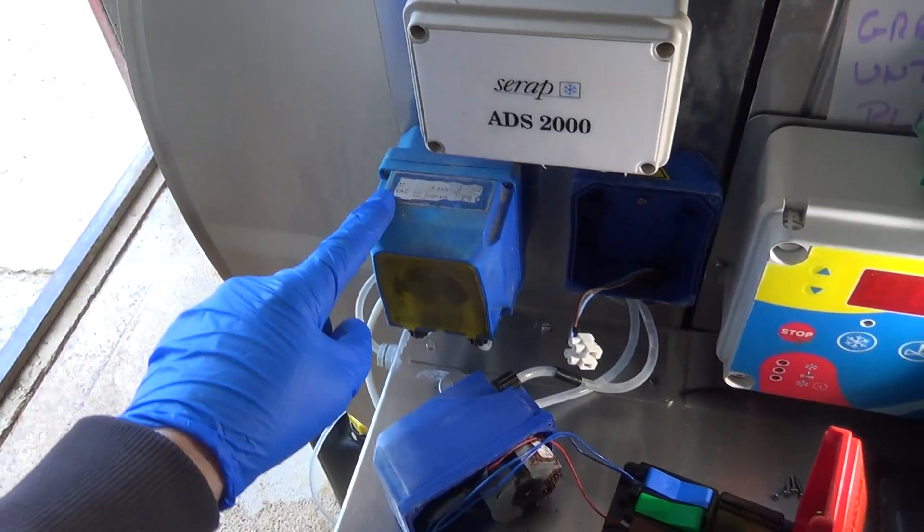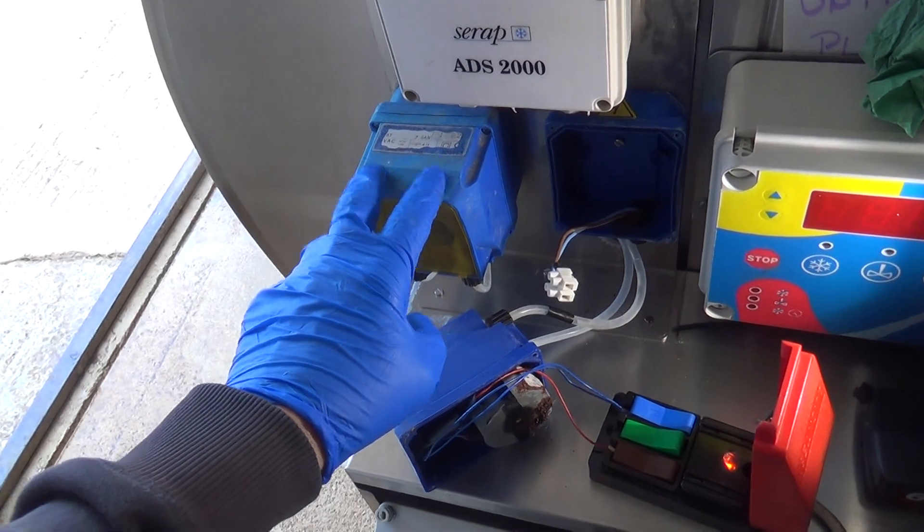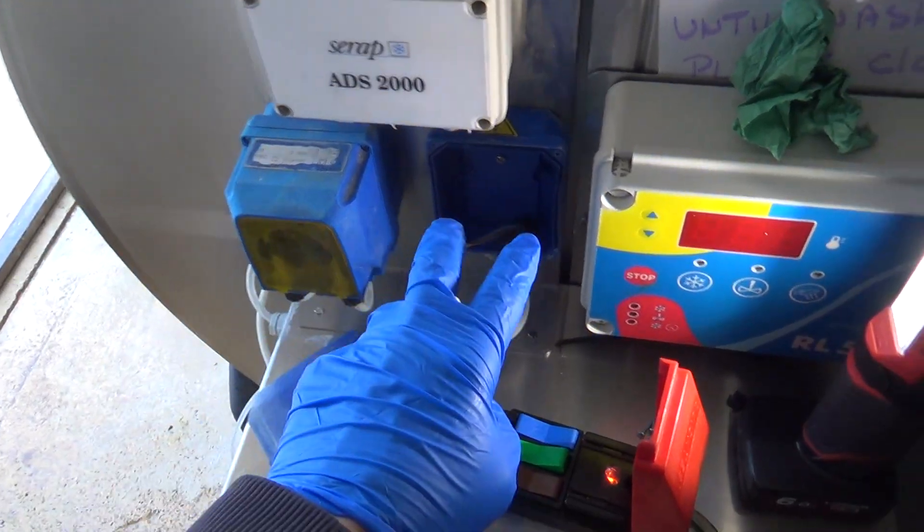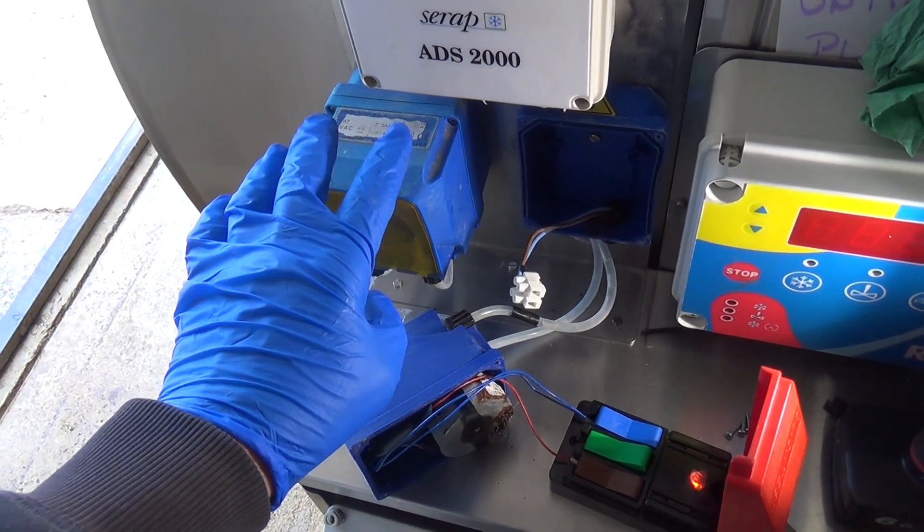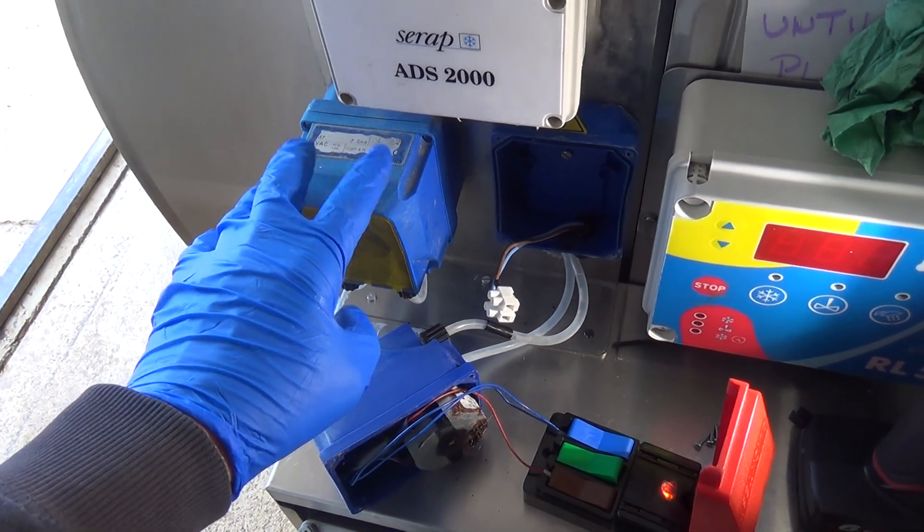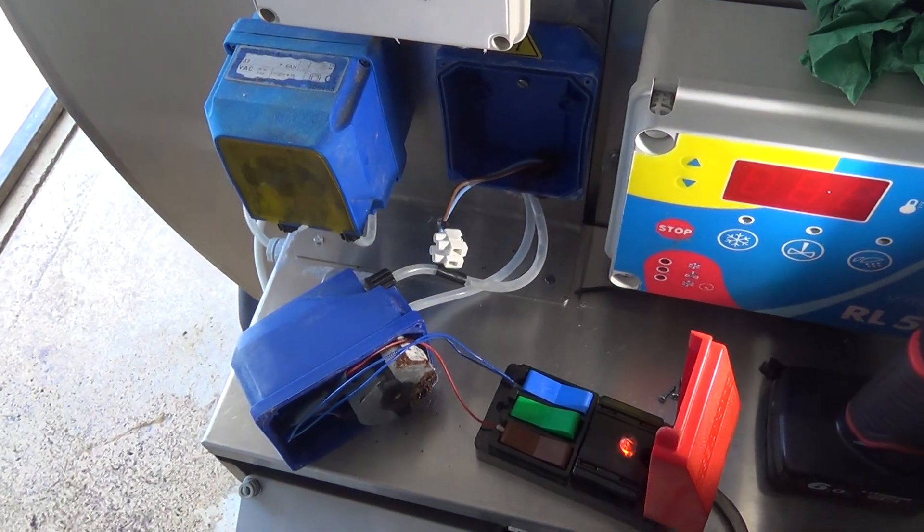It's got automatic dosing for the chemical. Some tanks have an alkaline pump and an acid pump and they alternate between them, so it'll do three or four alkaline washes which will get rid of the fat from the milk, and then they'll do an acid wash which will get rid of any limescale or milkstone.